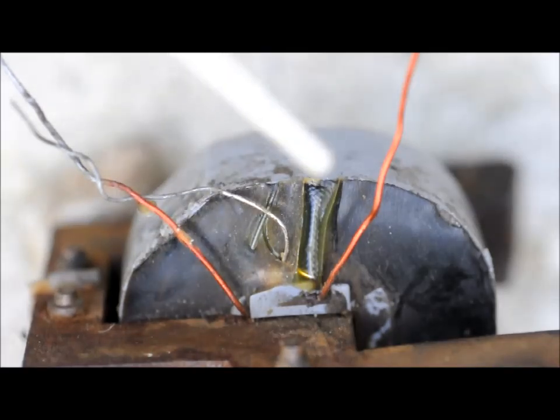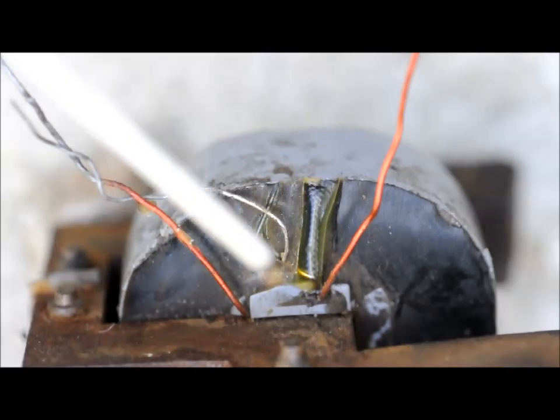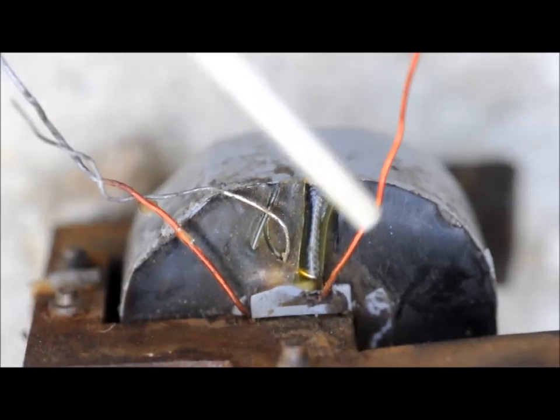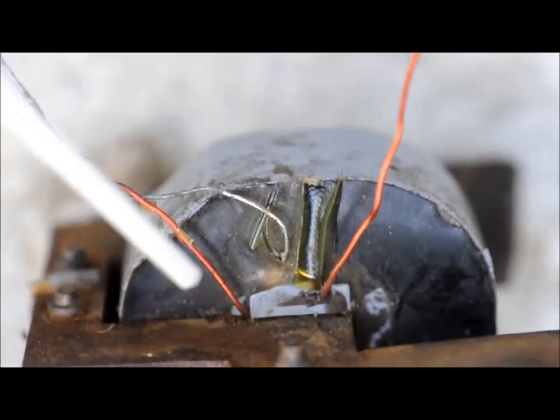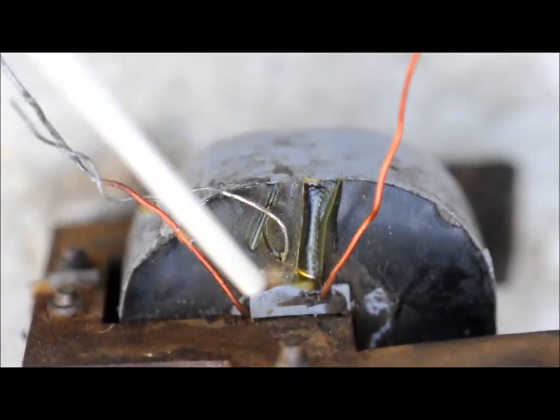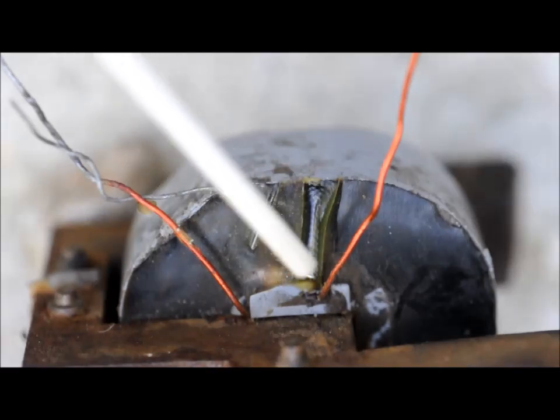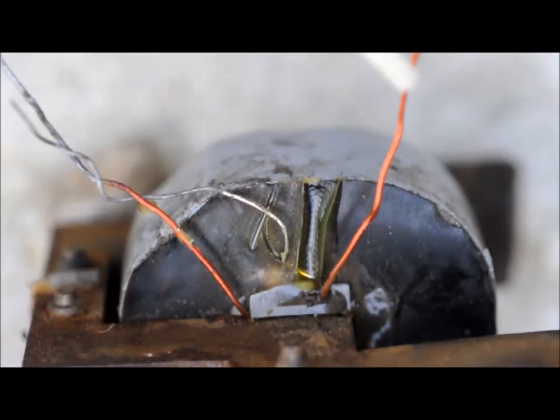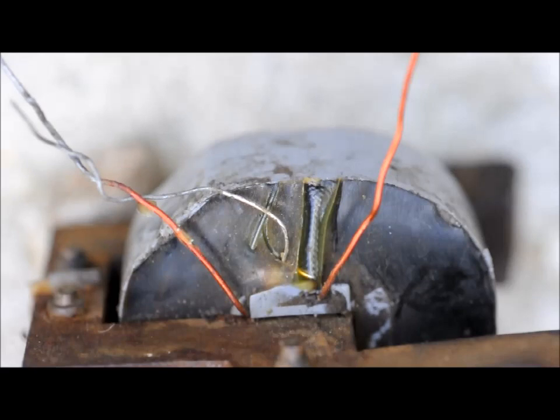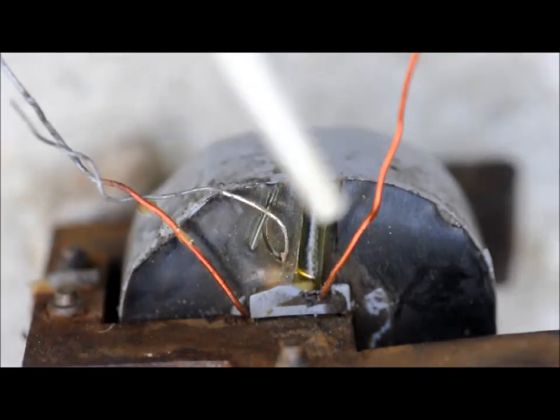Magnet wire is a solid copper wire, and it has a varnished coating on it for an insulator, and that's what the primary winding is made of. It carries a lot of current, so it's a pretty heavy gauge wire. I've never known them to fail, never even heard of one failing. So this is a very reliable winding.